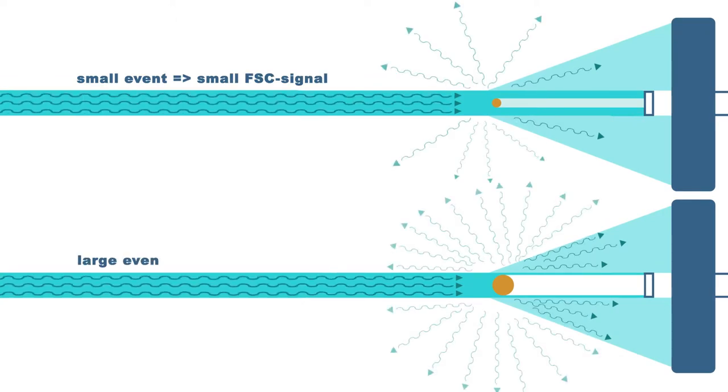The detector in the forward direction transforms the intensity of incoming light into an electrical signal. Appropriate detectors are linear over a wide dynamic range. A lower intensity of scattered light leads to a low voltage at detector output. A high intensity of scattered light leads to a high voltage of detector output.